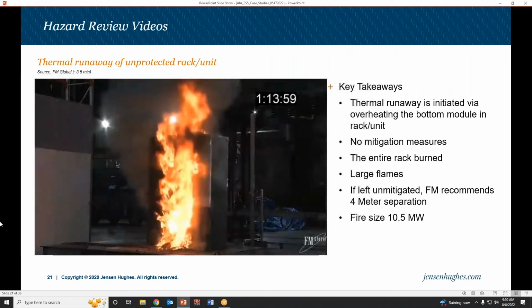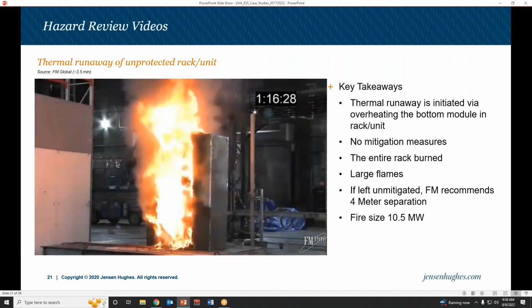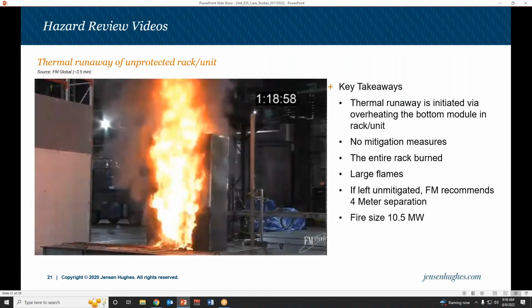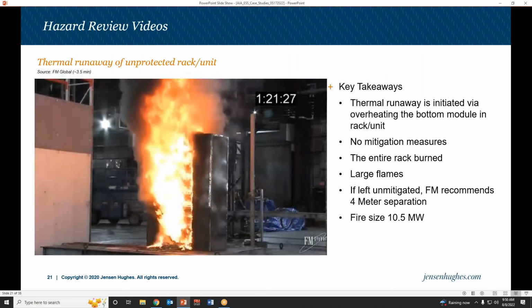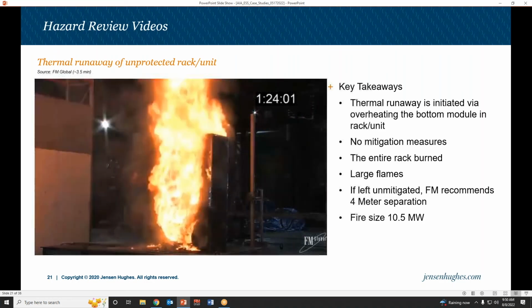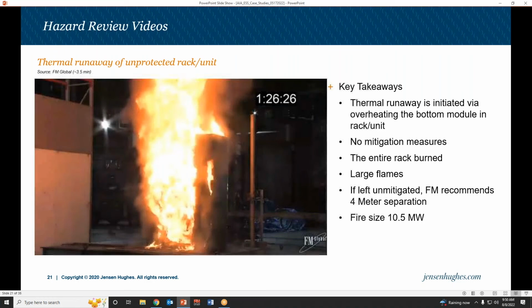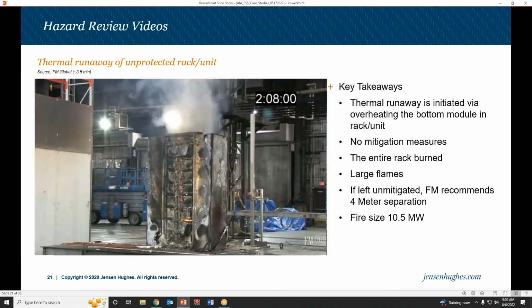That gives you an idea about the fire size. About 15 minutes in, they measured the fire size at about 10 megawatts. They do the same test with a sprinkler system on top, and they can control the fire to about 7 or 8 megawatts. They drizzle a lot of water on it, which makes sure the fire doesn't spread, but you're not going to put out that battery. As I mentioned, it's a thermal runaway—that battery will have to finish its burn.